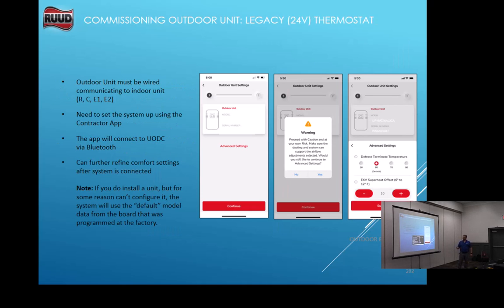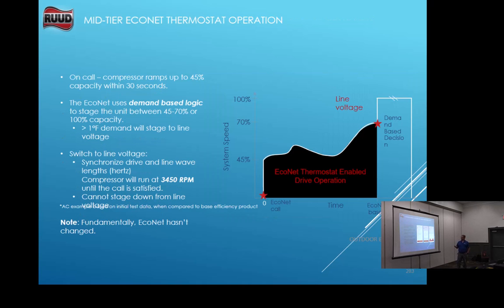We talked about commissioning of the outdoor. If you have an outdoor unit, you're going to commission it with the app outside, and it's going to go through and ask you everything that you want to do with it. If you have a mid-tier EcoNet thermostat, this is how it's going to operate. Some people have asked us this question. So from 0 to 45% is going to ramp up in 30 seconds to 45%. And then from that 45% to 70%, it's going to sit there and modulate just like that fully variable speed control compressor, up and down.